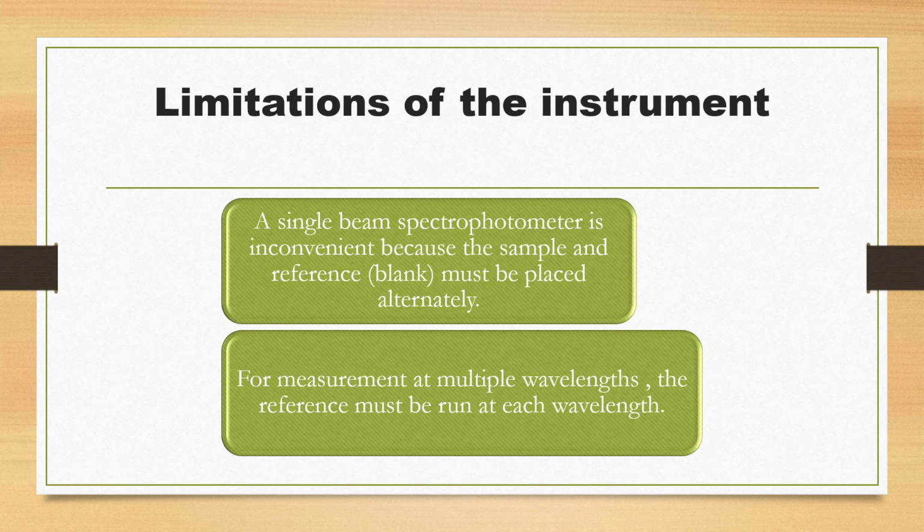For example, if you want to take a reading at 540 nanometer, you first put the reference and then the sample and then note the reading. And again if you want to take the reading at 550 nanometers, you have to place the reference and then the sample and then note the reading.